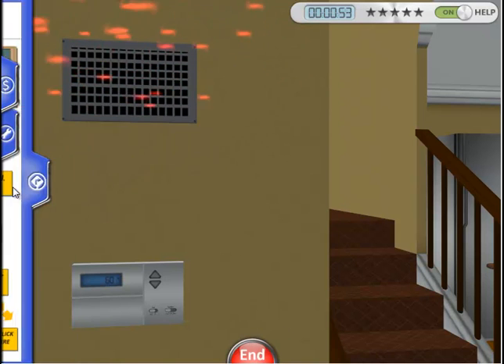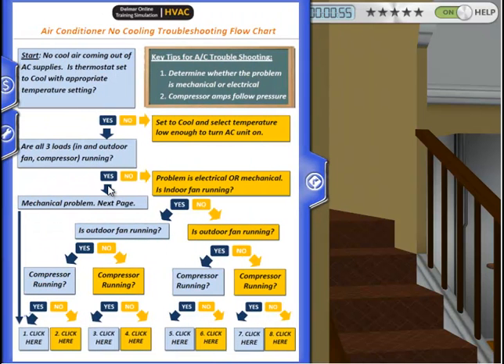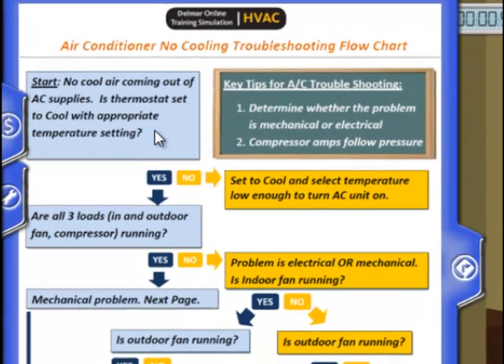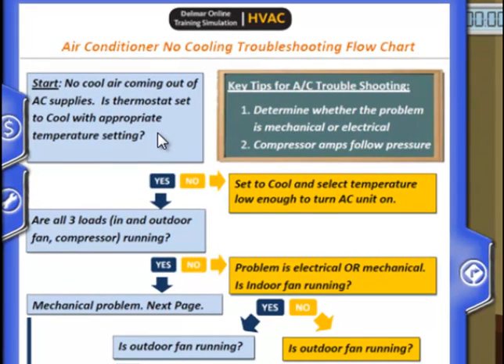Let's take a look at our troubleshooting guide to understand what the problem could be. The third tab on the left is the troubleshooting tab. We did confirm that the thermostat was set to cool with an appropriate temperature setting. The first major step in assessing an air conditioner is determining what loads are running. This includes the indoor fan, outdoor fan, and compressor. Troubleshooting usually employs a process of elimination, which will save time and money.